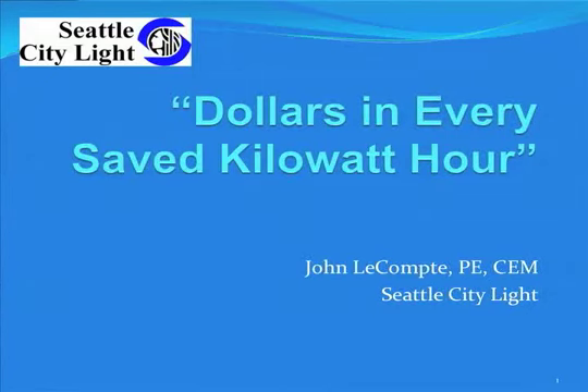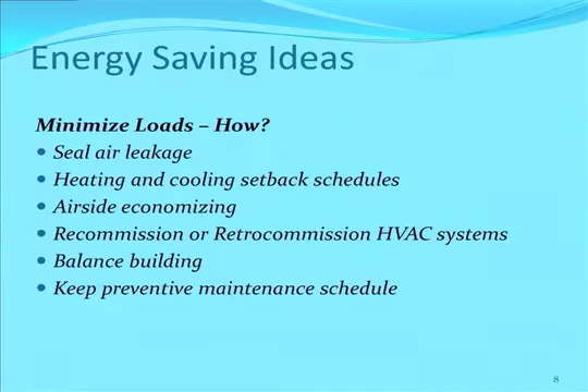Every bit of energy that you're not running through a wet cooling tower saves you water, so that's a multiplied effect. And how do we do that? One very good way is making sure that you seal your doors and windows, elevator shafts, and also your stairwells. Making sure that you have setback schedules and that they're appropriate to the occupancy of the building.